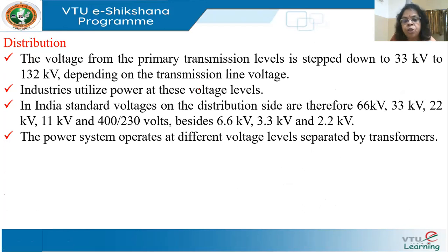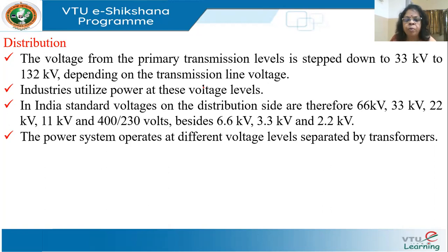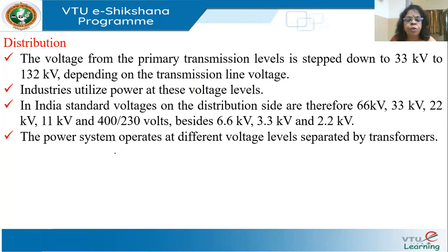During transmission, voltage is stepped up to 220 kV or 400 kV. For distribution, it is stepped down from 132 to 33 kV. Industries may evacuate power at around 66 kV or 33 kV, while domestic consumers normally require power at around 400 to 230 volts. Different countries have different distribution operating levels, such as 6.6 kV, 3.3 kV, and 2.2 kV.